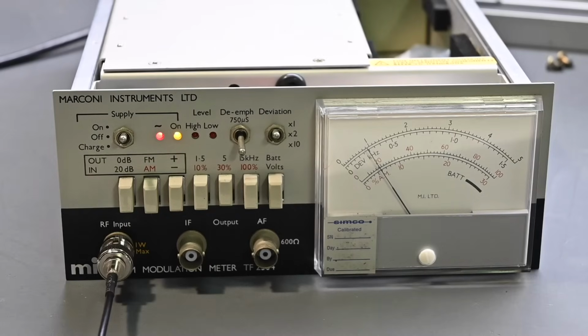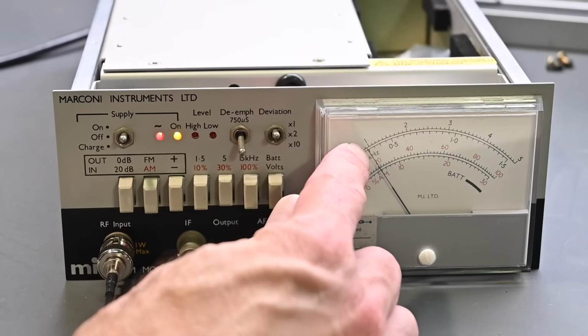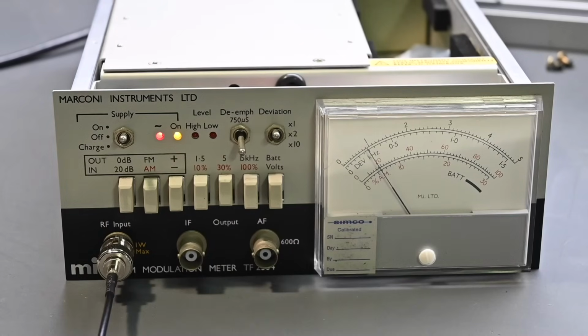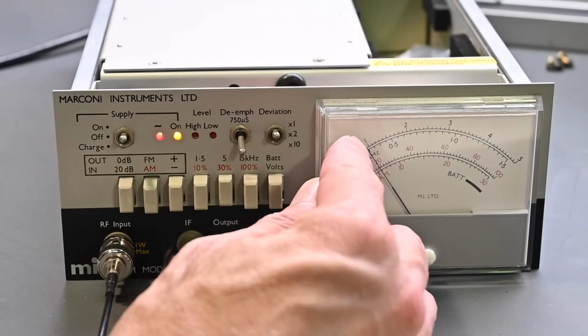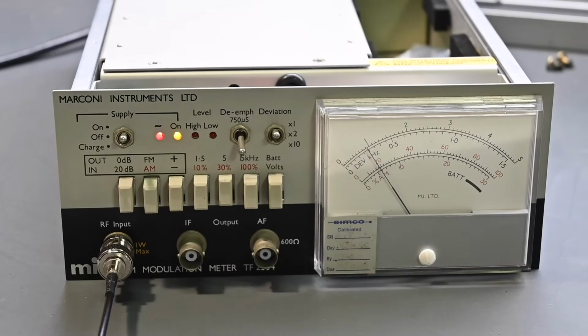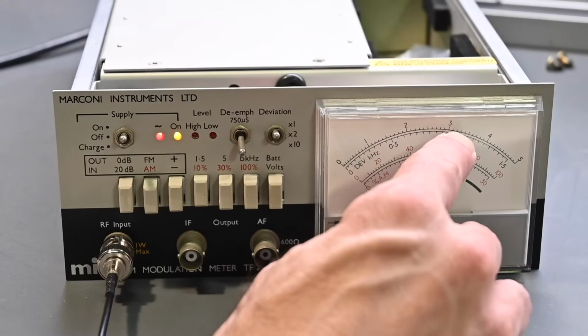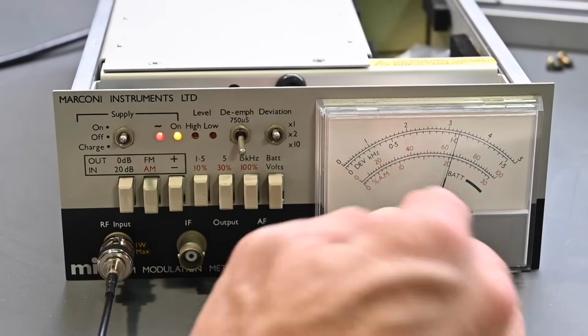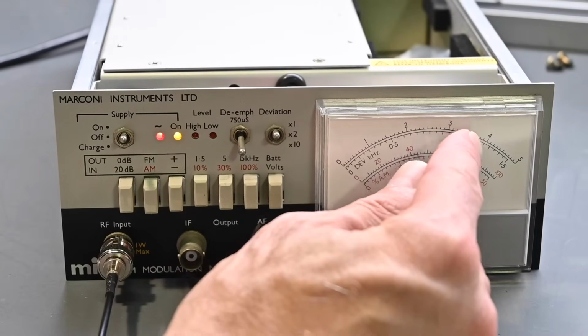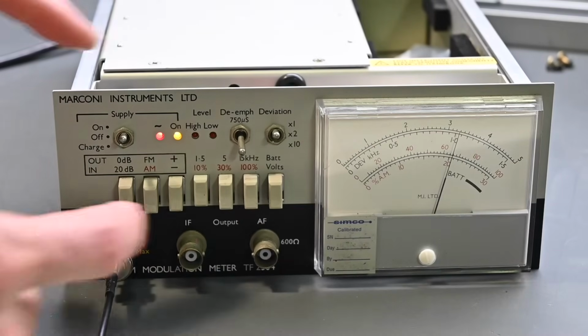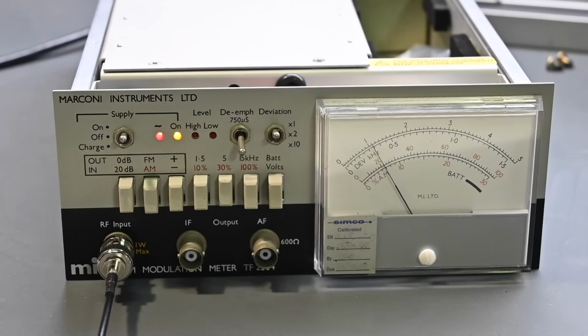So let me show you. Right now, it's sitting at 1 kilohertz, but it's just a little bit under. The signal generator is right on 1 kilohertz. But again, this is just slightly under, very, very close, not really a problem. If I go down to the next range below, you can see it's sitting ever so close to 1 kilohertz, but maybe just a tiny bit over. So on one range, we're a little under, one range, we're just slightly over, but both are extremely close. If I go back to the 5 kilohertz range, it's very close to the 1, but slightly under. If I go up to 2 kilohertz, now it's right on. I mean, that's extremely close, so no issues there.